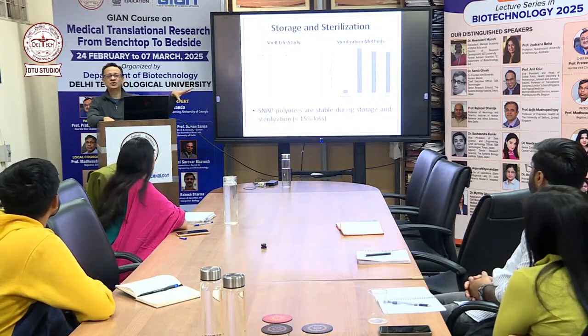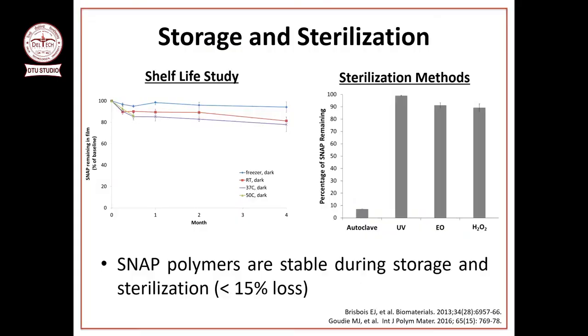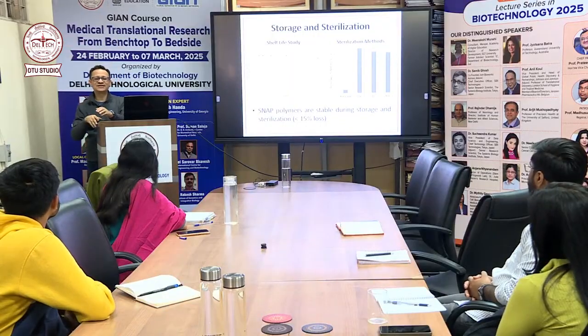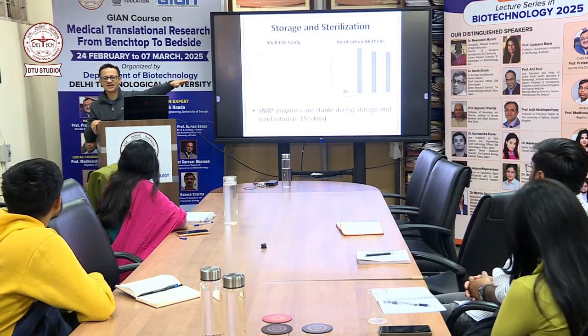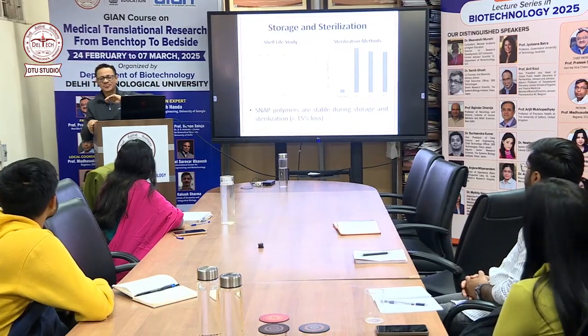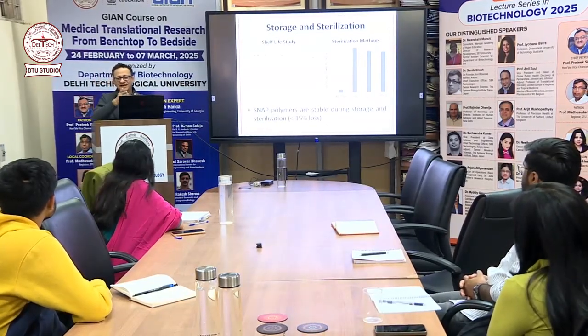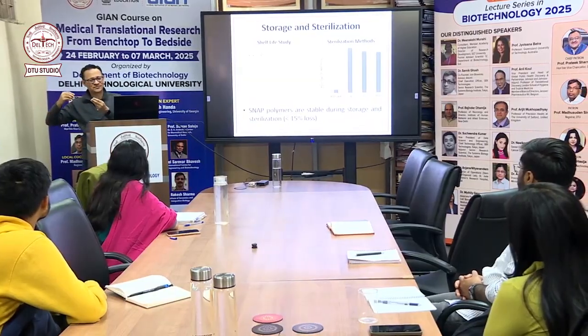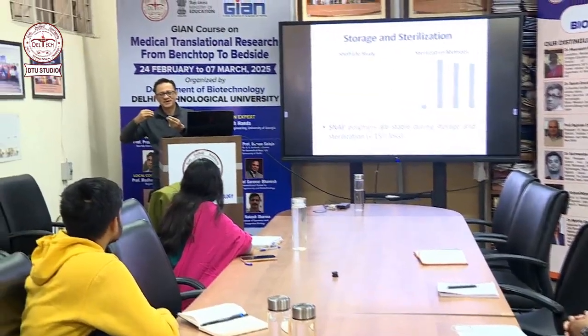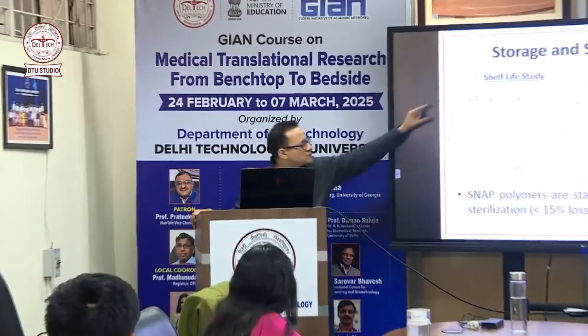Also, this study we did only to prove that if by chance a catheter is exposed to heat, see, a catheter should be sitting at room temperature on a shelf or, let's say, in a refrigerator. But if you are shipping it, it better reach wherever you are sending it within a week or two. Worst case, it's a month. You might lose 15% of NO, but then you can keep it in the refrigerator and you will maintain that level. It should not just be sitting at 50 degrees for 3 months. If that's the condition, then maybe this is not the best technology.